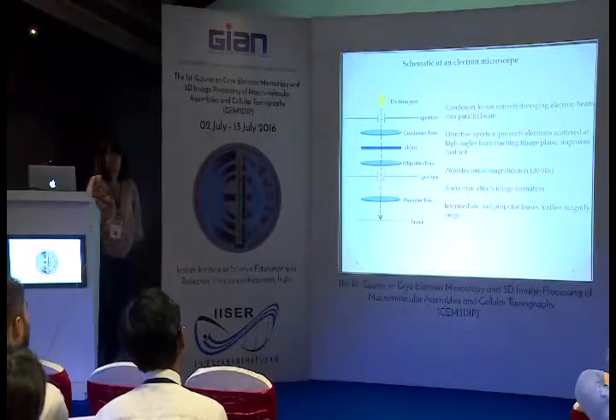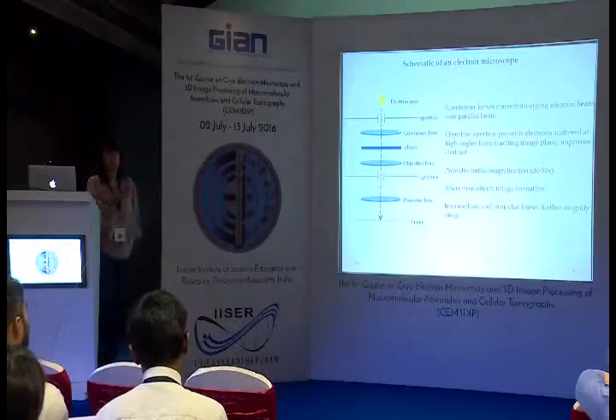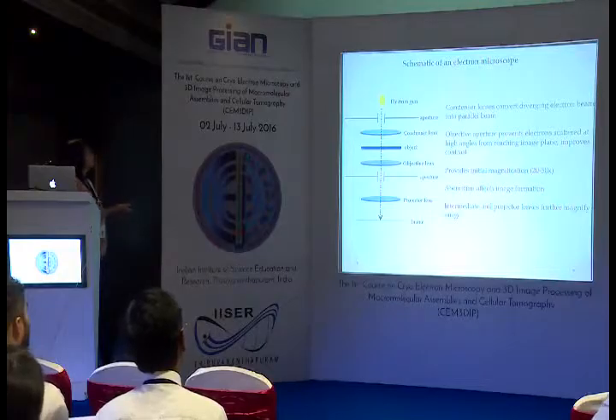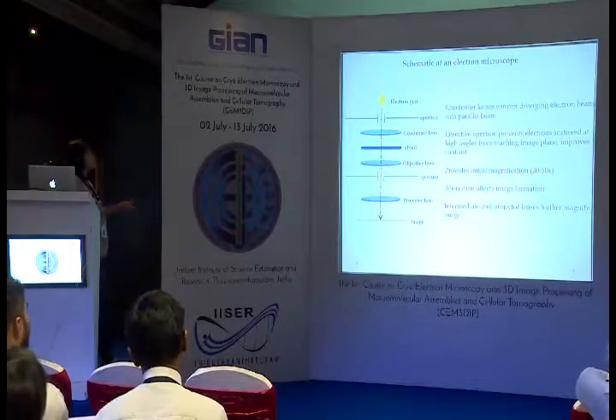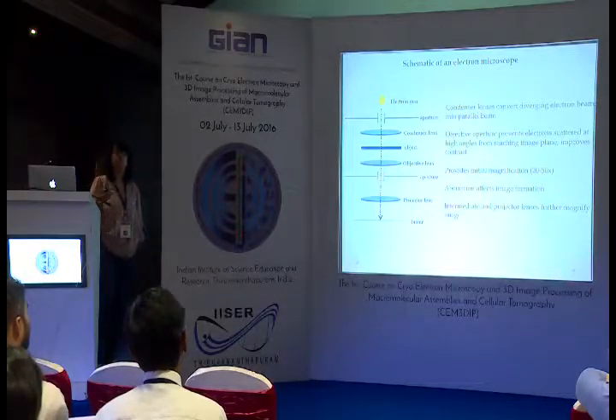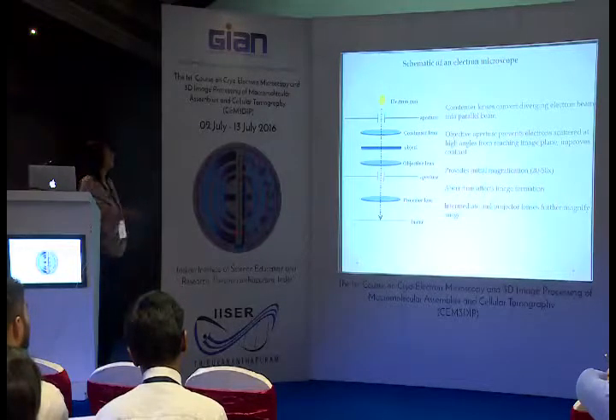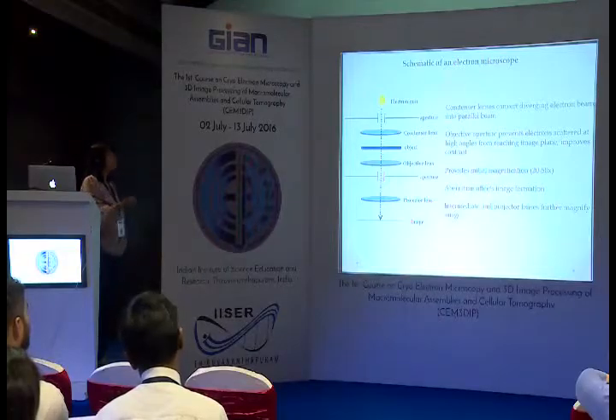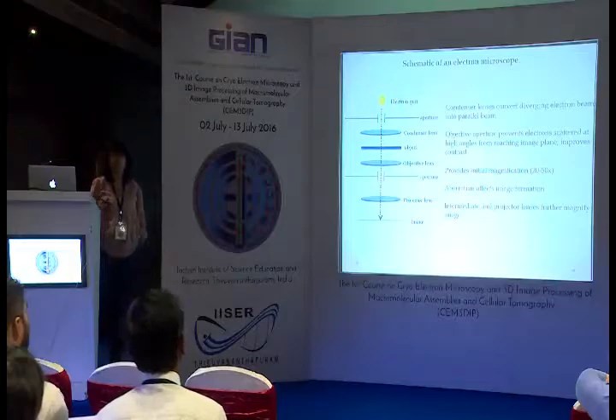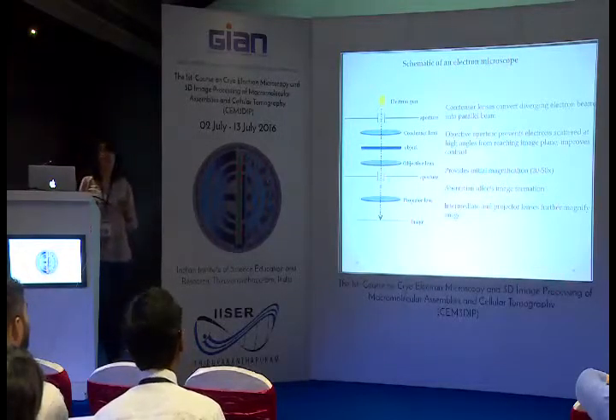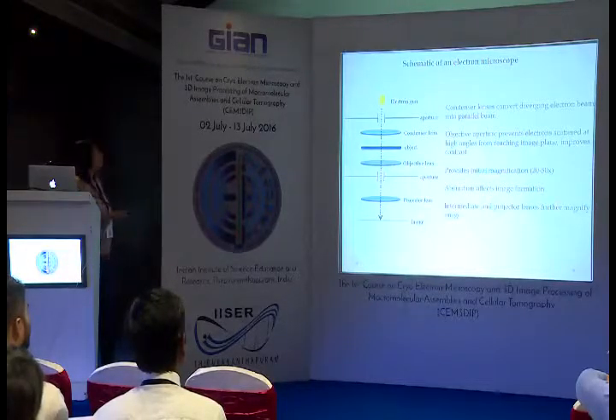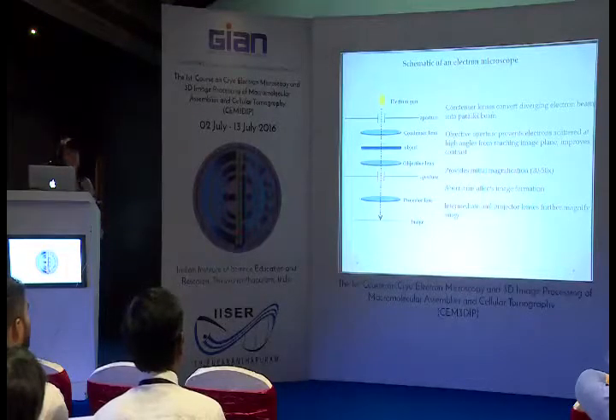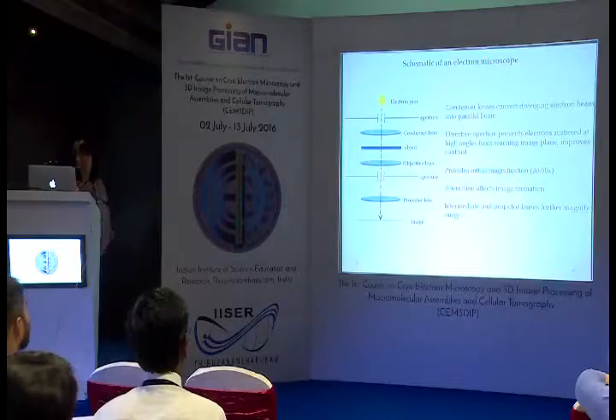After the beam interacts with biological objects, the scattered electrons undergo initial magnification by the objective lens. Apertures prevent highly scattered electrons from reaching the image plane and creating noise. A series of intermediate and projector lenses further magnify the image formed in the image plane. The detection system — whether film, CCD camera, or direct detector — determines how much information from the object is preserved.